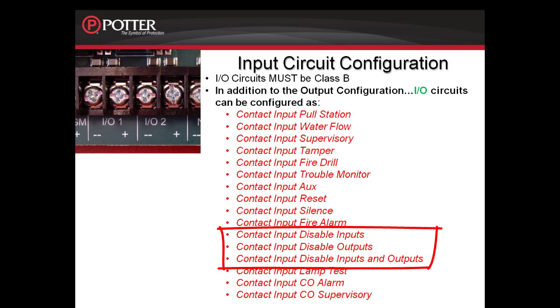Disable inputs, disable outputs, and disable inputs and outputs are used for monitoring a key switch or switch that when activated would disable the inputs assigned to the same software zone as the I/O circuit, or disable the outputs assigned to the same software zone as the I/O circuit, or disable both inputs and outputs in that same software zone. For information on programming that type of functionality, please refer to the recorded module on input and output disabling functionality.